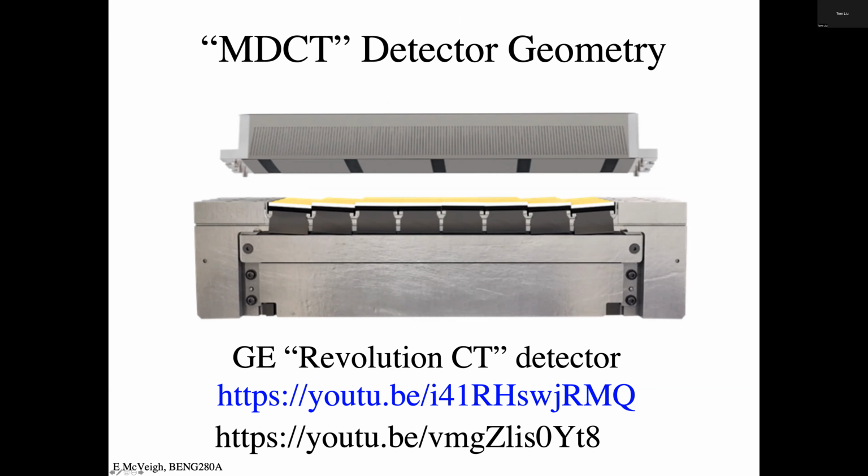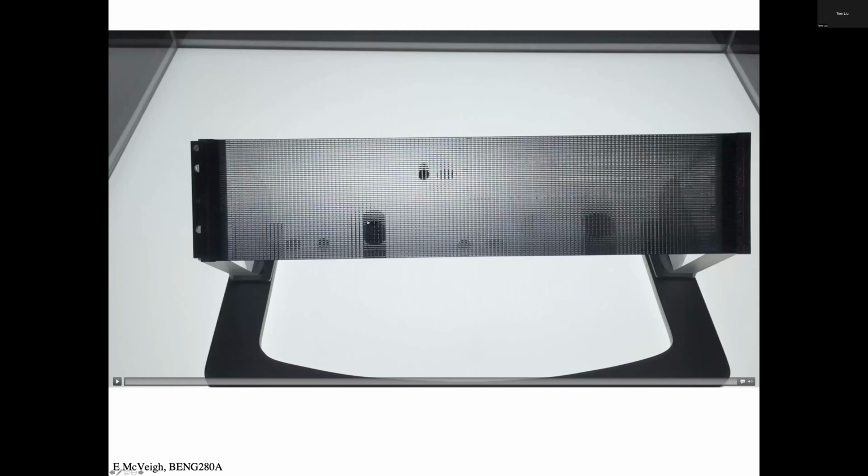Sitting above the detector, this thing, and we looked at this on the problem set, is the anti-scatter grid for this imaging field, which, remember, has a cone structure, right? So you can see through it if you're on a direct line of sight, but when you go to an angle, you can no longer see through it.